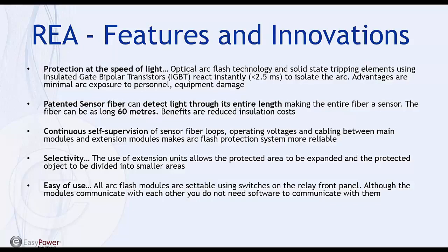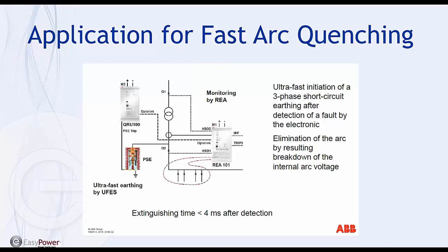Of course, the fastest arc flash protection possible is where you don't have to depend on the breaker. So if you look at the 2.5 milliseconds that the REA can operate in, and you use an ultra-fast earthing switch, then you can switch the arcing fault to a 3-phase to ground arcing fault, and then the current limiting fuses will blow, and that quenches the arc. So this is less than 4 milliseconds after detection, and it's by far the fastest way to eliminate an arc.